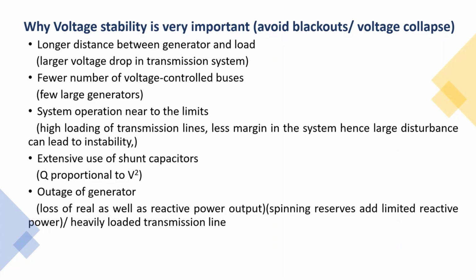So the kind of issue that we have is that our generator is located on this end, and there is a significant amount of transmission line in between, and there is a load at this end. So our load centers are there and generator centers are located quite far away. This is one of the challenges that we as a system operator face. So you have to provide adequate reactive power support between the load and generation, between all these substations, so that the voltages can be maintained and you are able to transfer that much active and reactive power safely into the system from the generation to the load center.